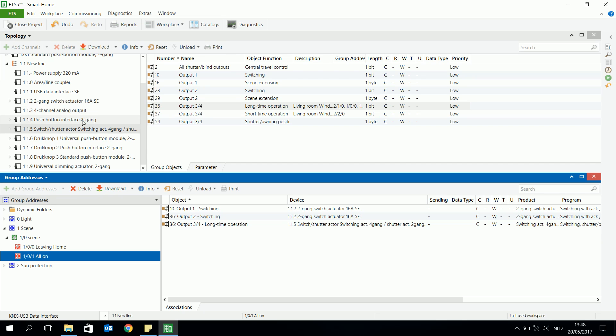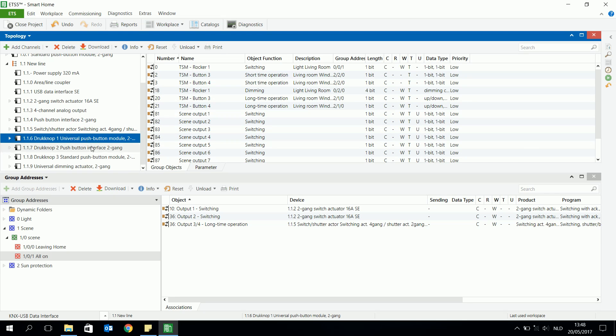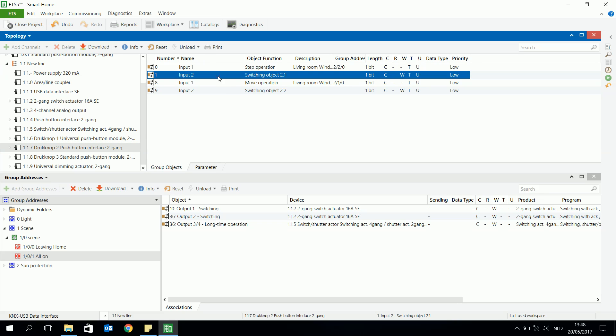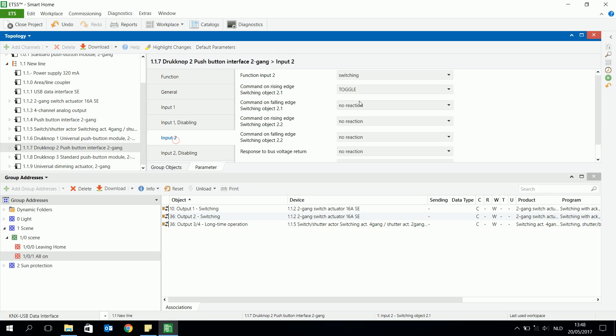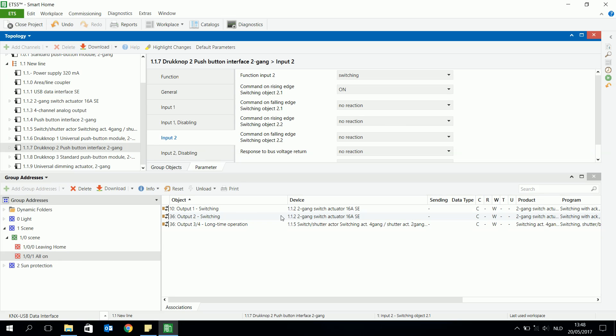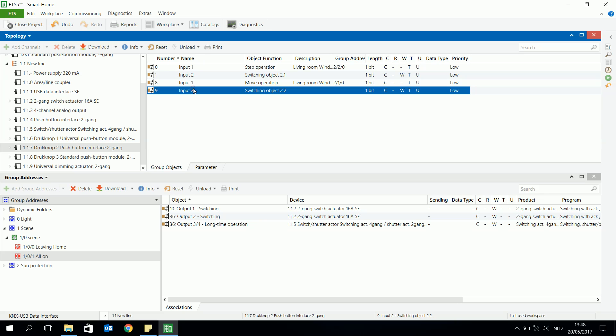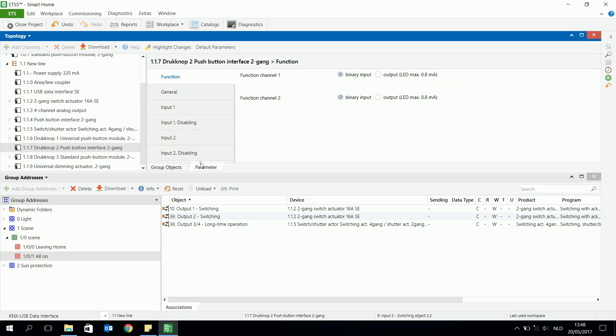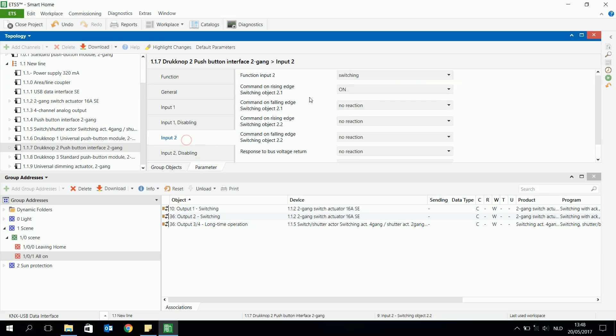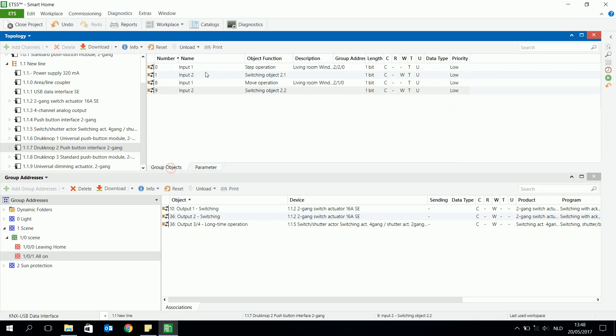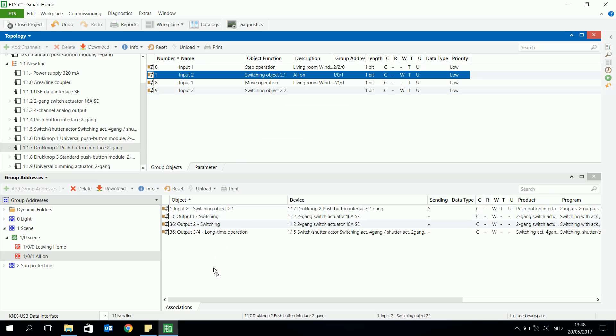I will use another button — I'm looking for which one is free — input two, to send an on signal, because I want to turn on all the lights. Then I will link the inputs; I have to be careful which one I chose. I chose 2.1, and I will link it to this group address. In this way I made the group address scene with one push button, which will send an on signal to those objects of the actuator.